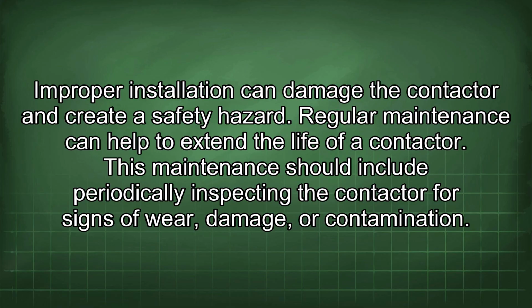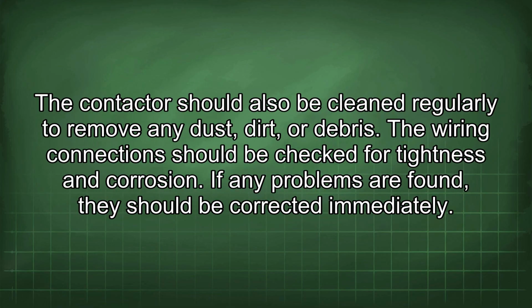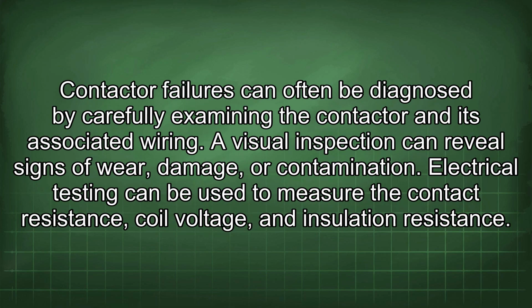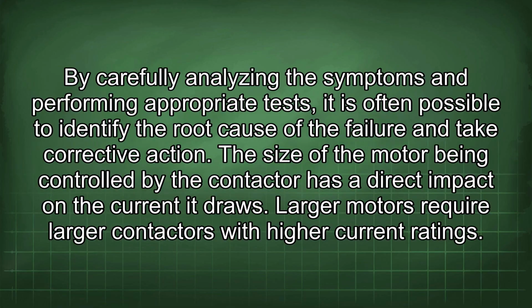Regular maintenance can help to extend the life of a contactor. This maintenance should include periodically inspecting the contactor for signs of wear, damage, or contamination. The contactor should also be cleaned regularly to remove any dust, dirt, or debris. The wiring connections should be checked for tightness and corrosion. If any problems are found, they should be corrected immediately. Contactor failures can often be diagnosed by carefully examining the contactor and its associated wiring. A visual inspection can reveal signs of wear, damage, or contamination. Electrical testing can be used to measure the contact resistance, coil voltage, and insulation resistance. By carefully analyzing the symptoms and performing appropriate tests, it is often possible to identify the root cause of the failure and take corrective action.